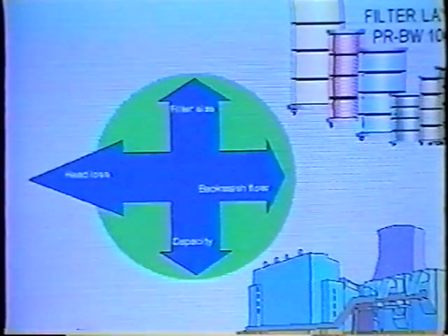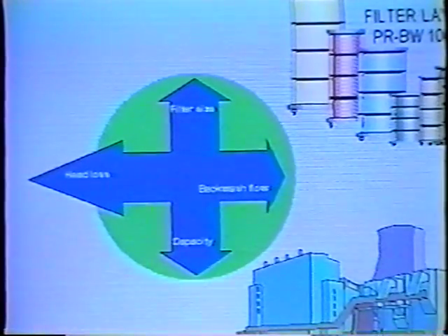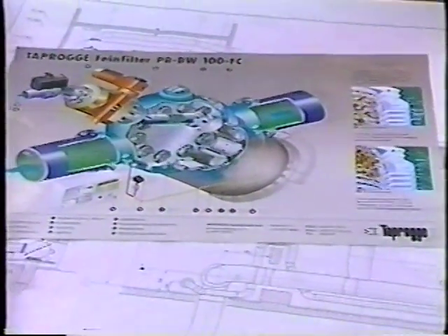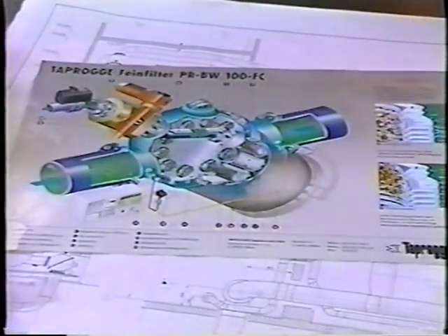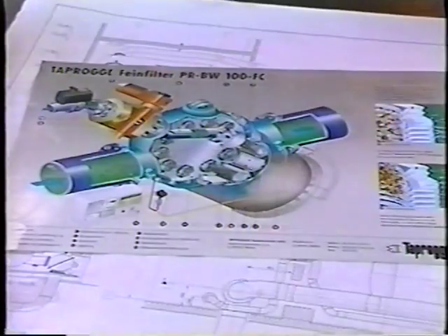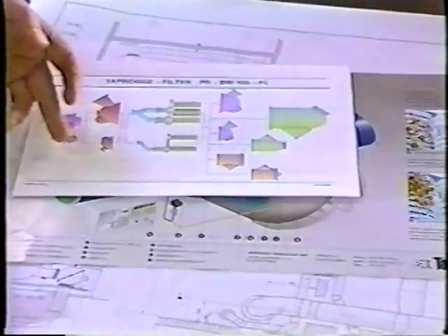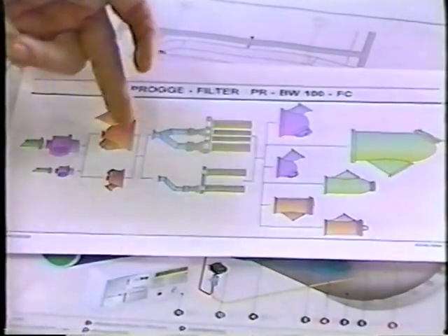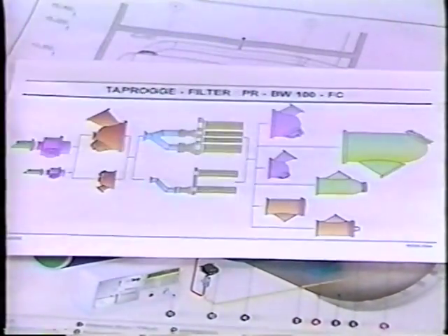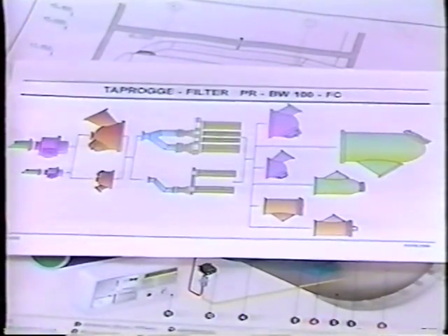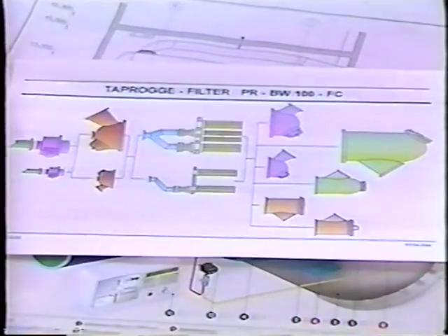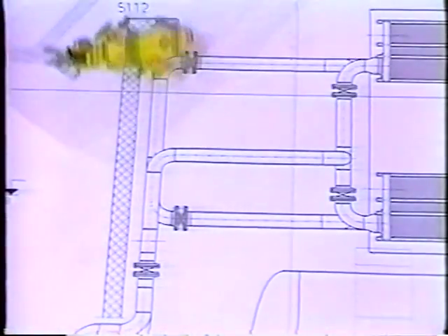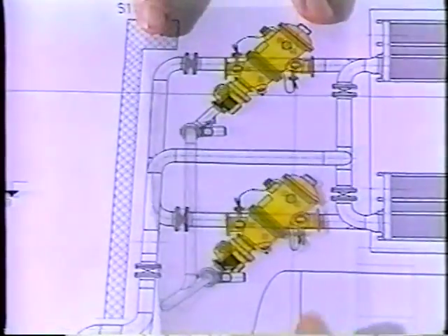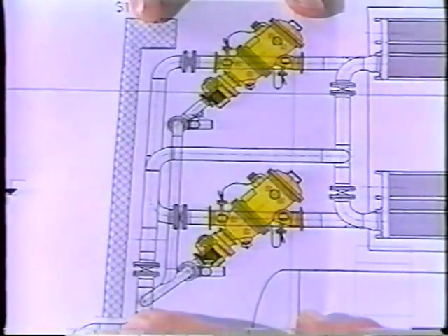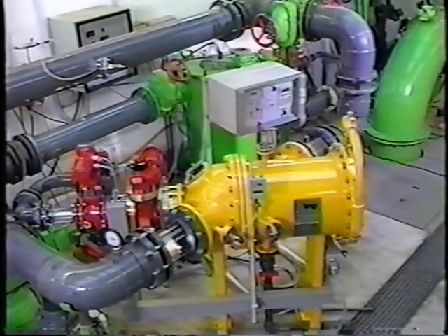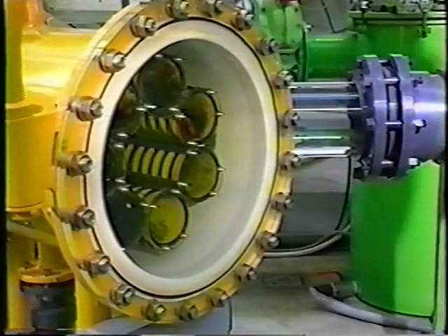All customers know their technical and economic operating priorities. Once the requirements have been identified, Taprogge will design a custom-made filter to suit the particular application. Diameters from 100 to 1200 millimeters, a range of inlet housings, single or double bank installation, outlet housing in hemispherical or cylindrical design can be implemented without problem due to the Taprogge modular system. This enables Taprogge filters to be installed at any point in the cooling water system. The Taprogge Pr-Bw 100FC is the solution for all fine filtration problems.